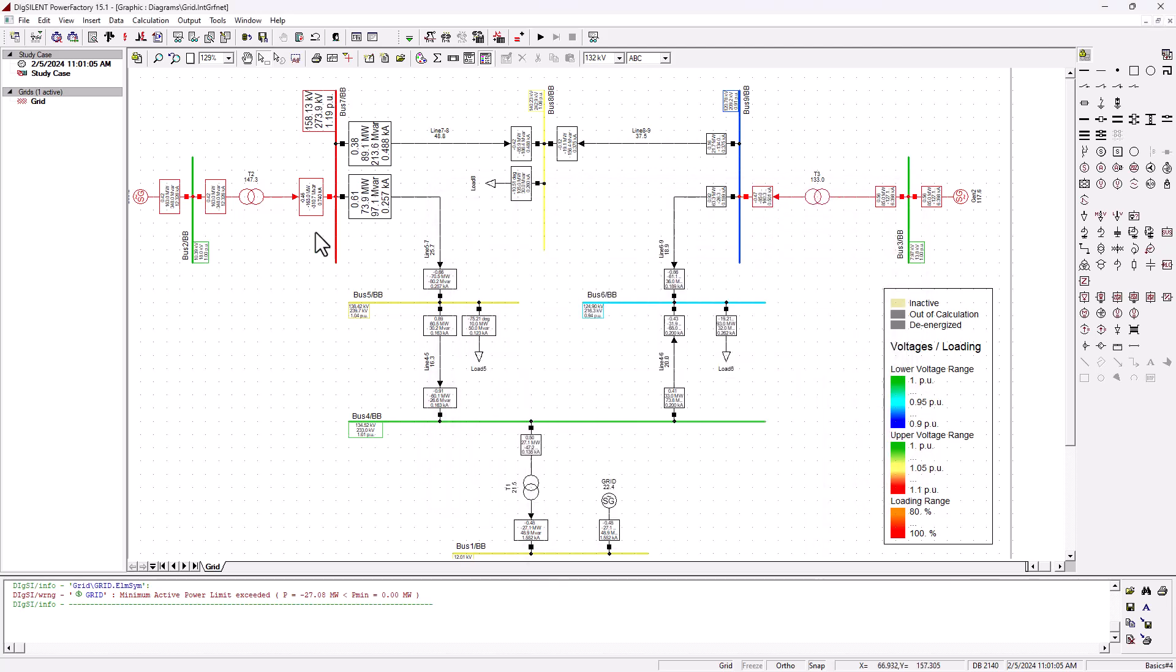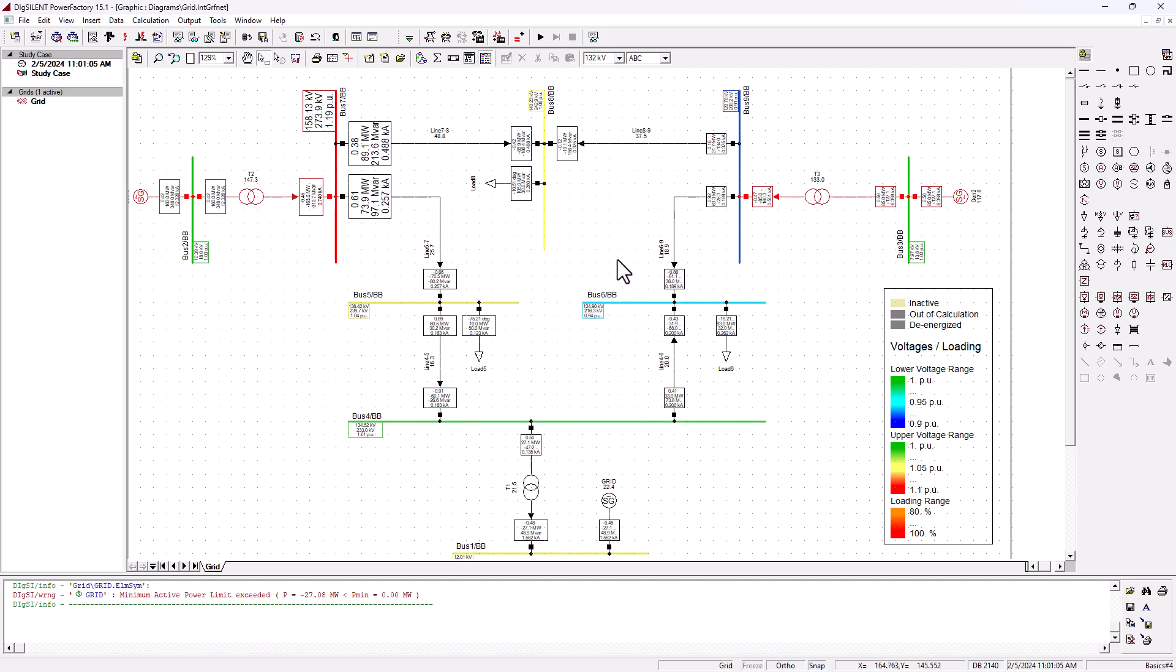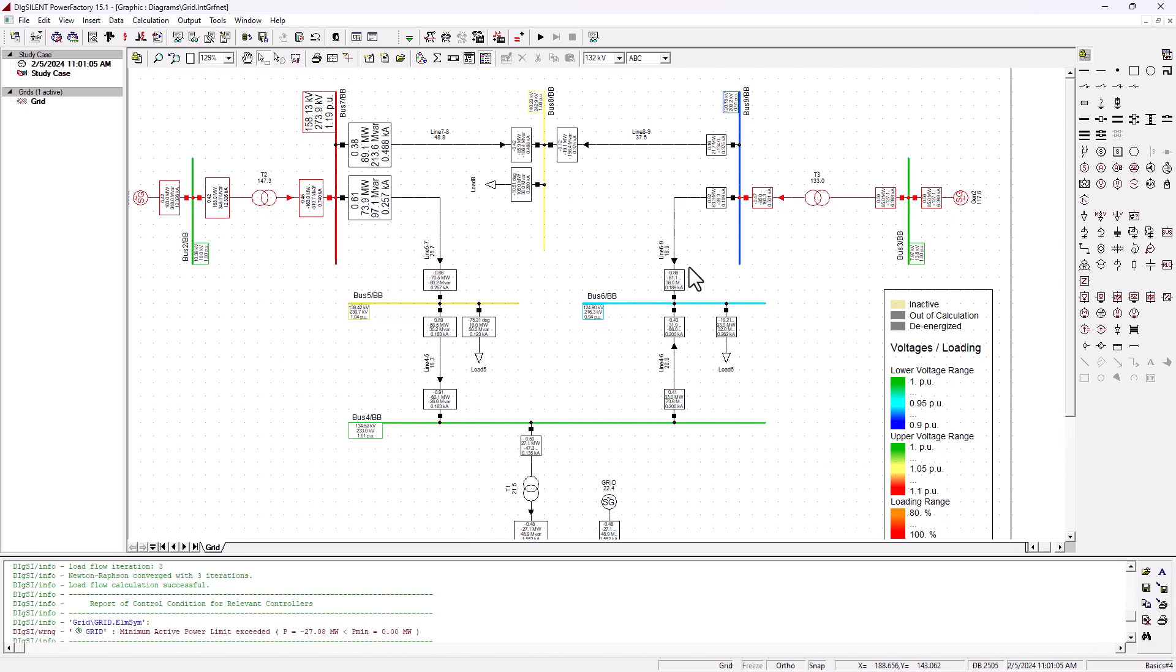That's 384 megavolt-ampere, but the transformer here is only 200 MVA. Automatically, we can see that this transformer is being overloaded. How do you avoid all of that? You start charging people for reactive power that they are dumping onto the system because that's causing problems.